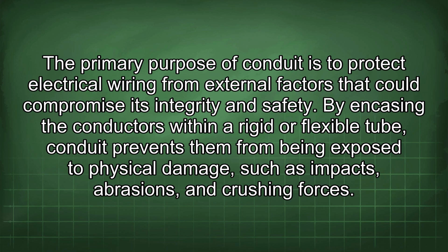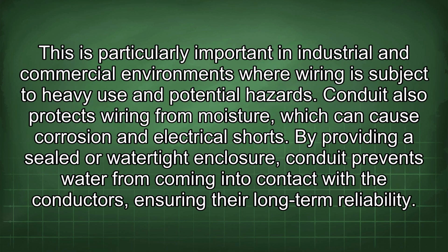The primary purpose of conduit is to protect electrical wiring from external factors that could compromise its integrity and safety. By encasing the conductors within a rigid or flexible tube, conduit prevents them from being exposed to physical damage such as impacts, abrasions, and crushing forces. This is particularly important in industrial and commercial environments where wiring is subject to heavy use and potential hazards.